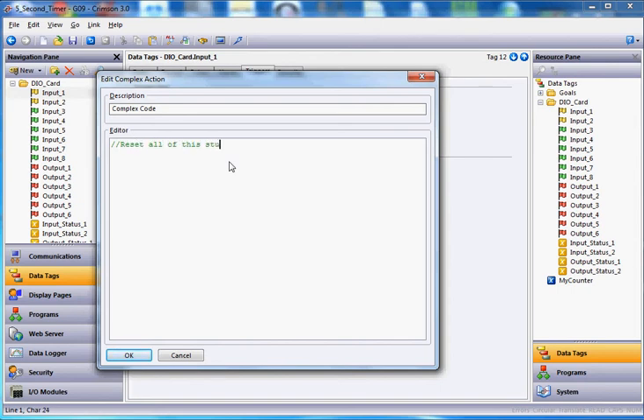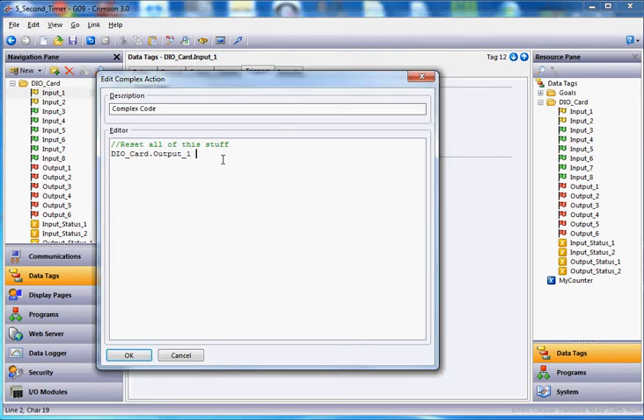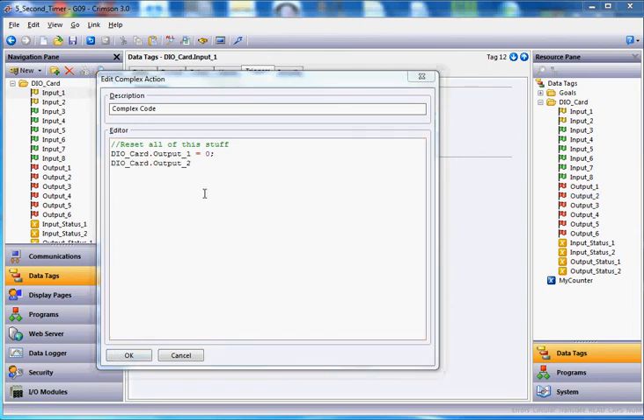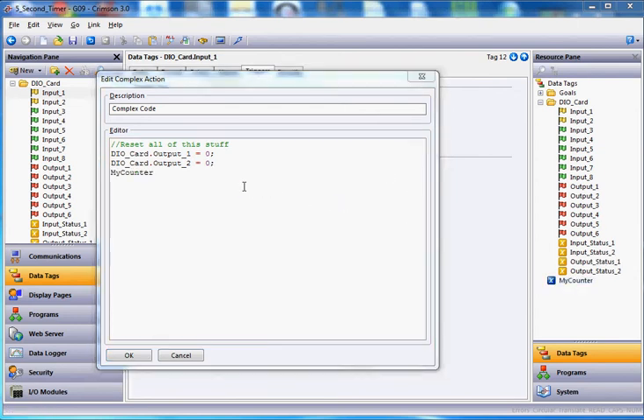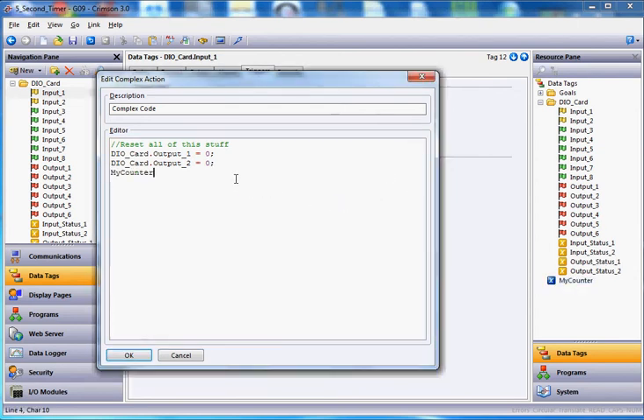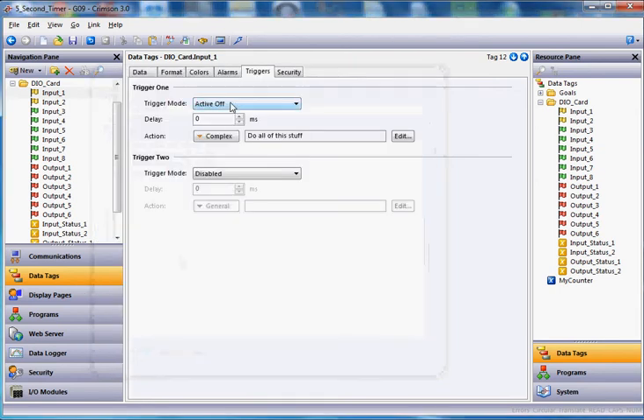And I'm going to basically type a little text. I'm going to say, basically, I'm going to go ahead and turn off output one. So I'll drag that over here and I'll say equals zero, semicolon enter. And I'll drag digital output two right here, zero, semicolon enter. And I'll drag the my counter out here so that we can reset it as well. All right, if this is all correct, I should be able to do the okay button, but I'm going to change this up here and type, do all of this stuff. We'll click the okay button, it accepted it. Active off here means it has to transition from being on to the off state, so that's what's going to happen here.